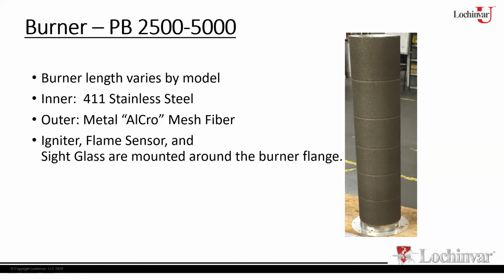Now, if you want to use water, some people always ask about using water to clean the burners. Here's the thing, with either the ceramic fiber or the AlCro mesh, if you use water to flush it out, blow it out with air afterwards, especially the ceramic fiber. The fibers can have a tendency, if it stays wet for long periods of time, can start to break down. But also with the AlCro mesh, it will rust if water sits on it for a long enough period of time. And it would take a while for that to occur, but it can rust.